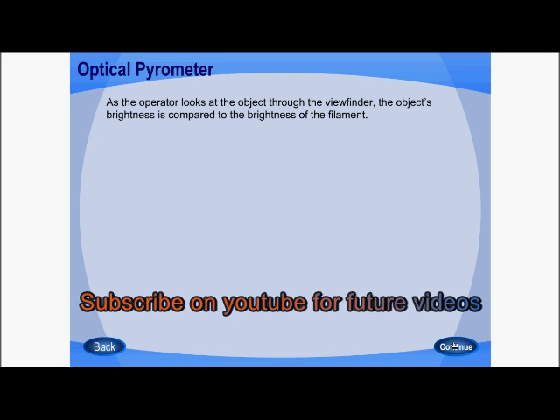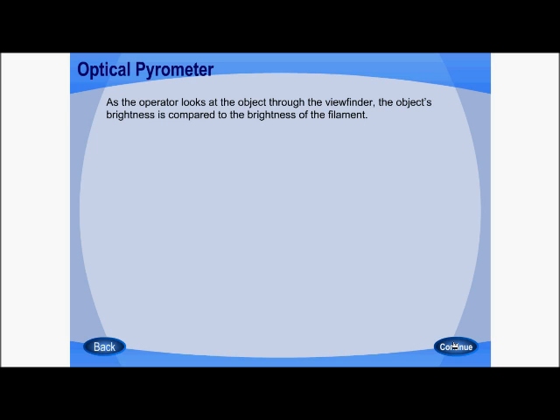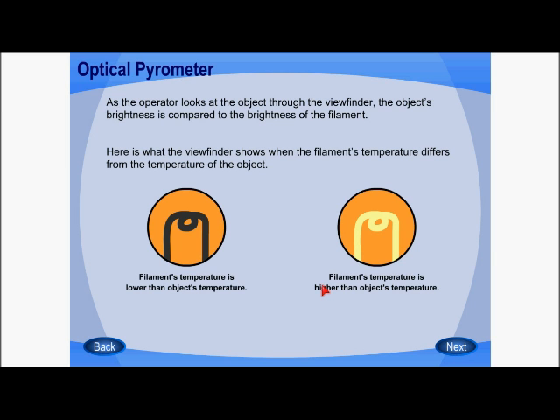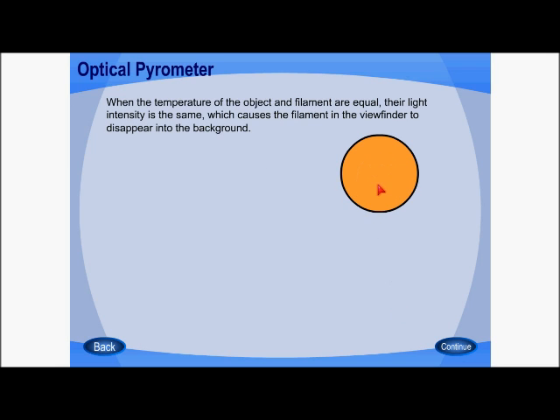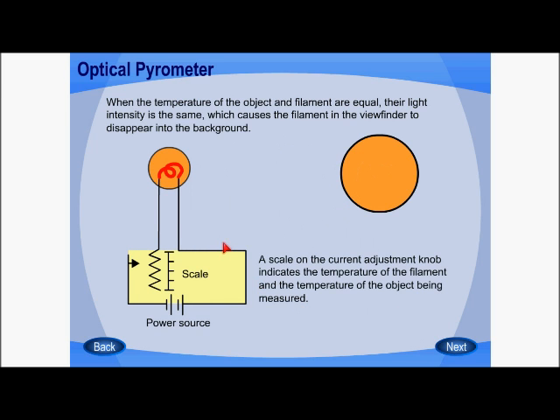As an operator, we have to look through the viewfinder and compare the brightness of the filament and the object. If the filament temperature is lower than the object temperature, we can clearly see the filament, which will be darker in color. If the filament temperature is higher than the object temperature, the filament color will be brighter than the object. We have to adjust the filament so that its color matches the object color, causing the filament to disappear into the background in the viewfinder.